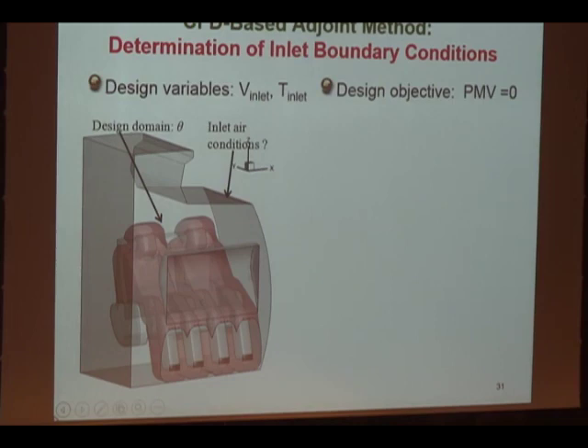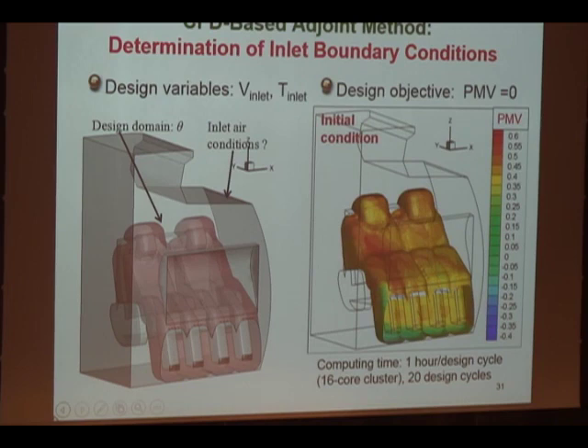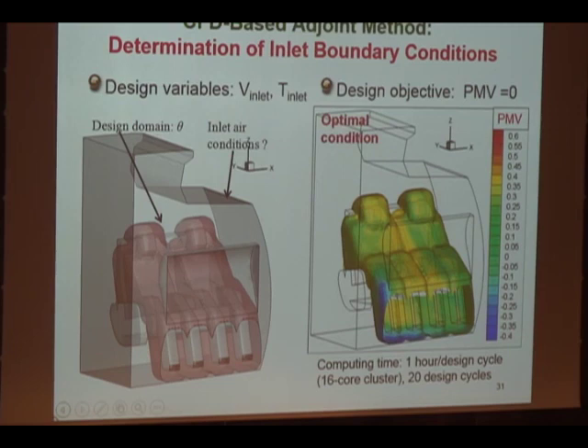Starting with conventional conditions, you can see the initial PMV is not very good — about 0.5. That's the current design — even in first class, you don't really feel very comfortable. But then we can change it. You see the color changes from red to yellow, to green, and finally blue. The final optimal design is more or less green — PMV close to zero. What we do here is change the supply velocity and temperature, and this final velocity, temperature, and supply angle is automatically calculated with the adjoint method.